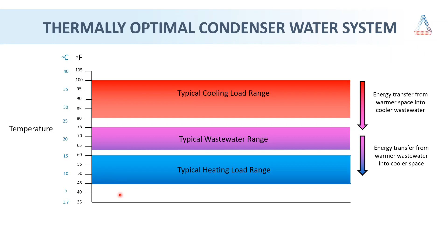So looking at that, we have a little chart here to show thermally optimized condenser water systems. You can see over the seasons how the big swing can occur when you're looking at geothermal fields, otherwise boiler systems, and then finally wastewater temperatures. This is just one quick example of a geothermal field that over the seasons will see roughly a 40 degree Fahrenheit swing. It can be even higher or lower in that case and see a bigger overall delta T.